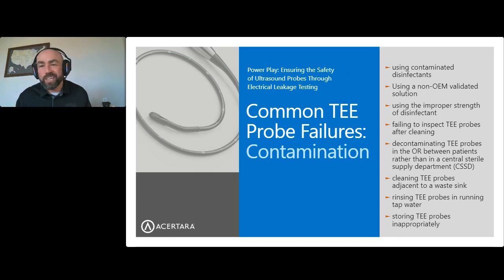So how is it that these probes tend to fail, or what do we do that leads to those kinds of things? Using contaminated disinfectants. You want to look at those disinfectants and apply all the same disciplines I'm sure that you use with other disinfecting solutions. When was it opened? How long is it good for? How many times am I allowed to use it? Making measurements with test strips to ensure, obviously, that the disinfecting solution is still suitable. Using non-OEM validated solutions or the improper strength of disinfectant is also an area of issues. And failing to inspect, I think we've talked about some of the challenges there and why inspection is important.